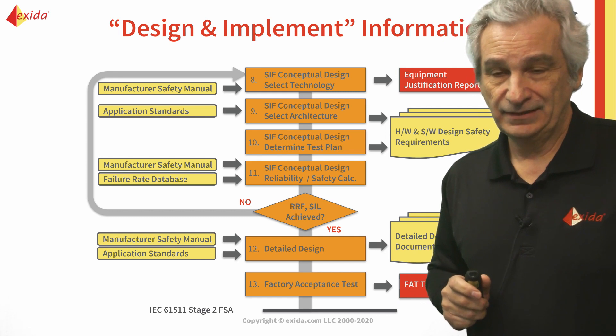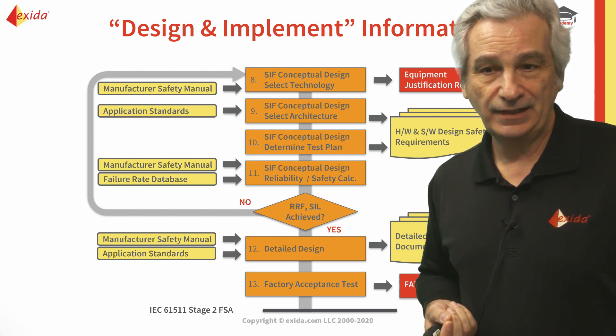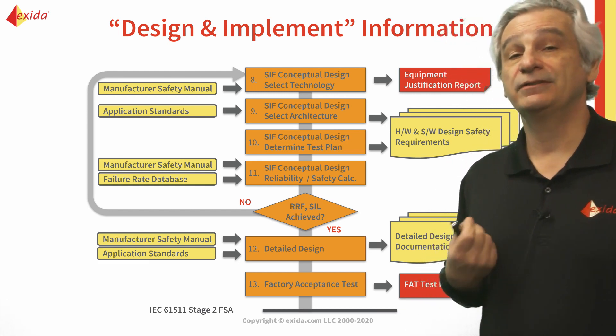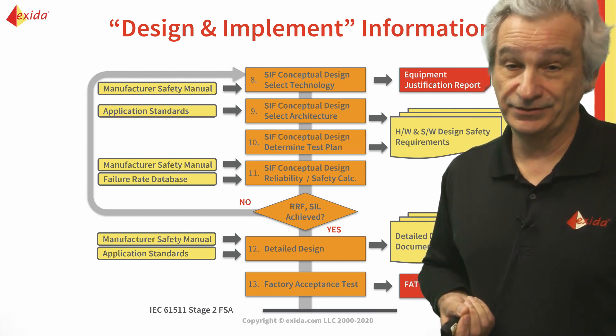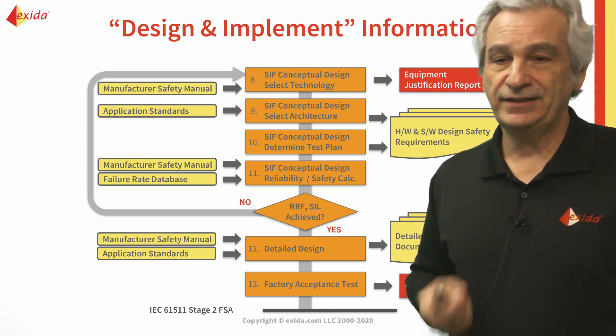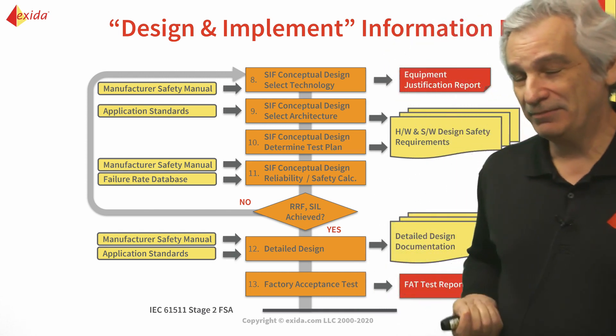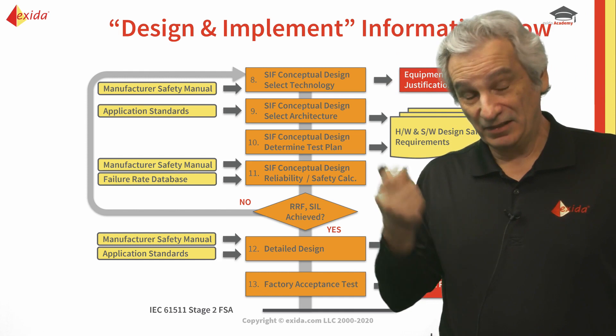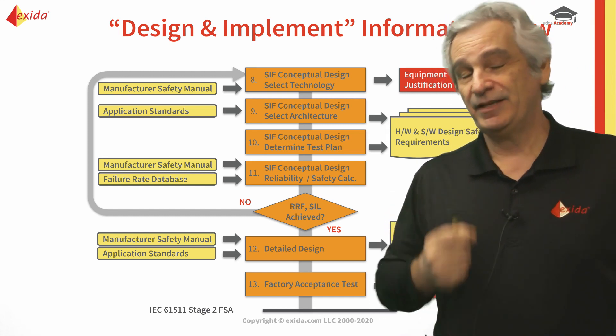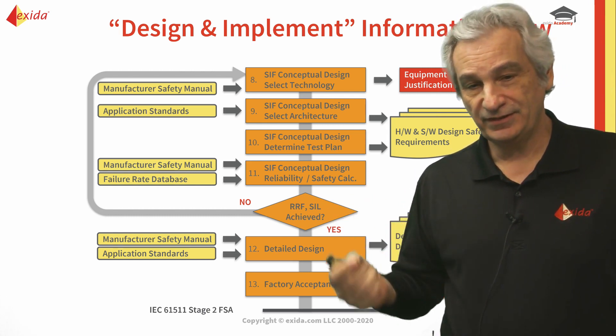Once we've selected our equipment and system, we need to think about how we're going to test it, and we need to think about the architecture for the design — are we going to use redundant components, are we going to do online testing? All of that needs to be considered. You'll notice on the left-hand side: manufacturer's safety manual. One thing I like to get the class to remember is to 'read the flaming manual' — RTFM.